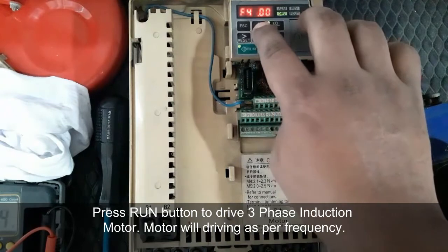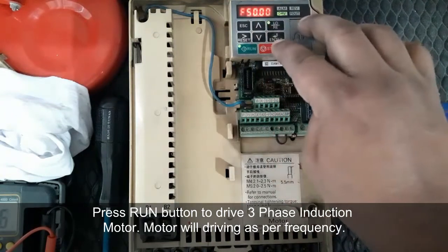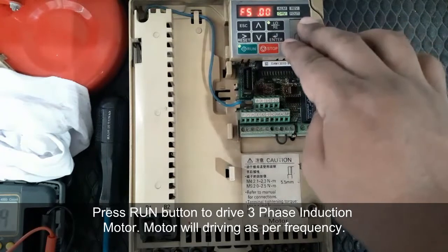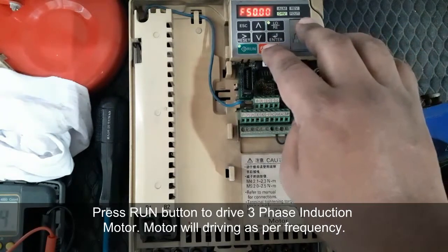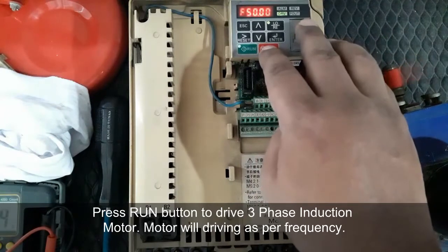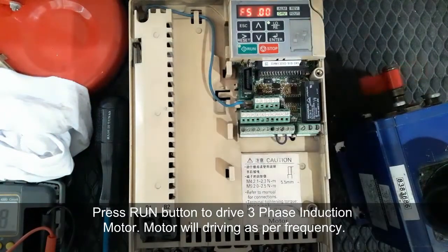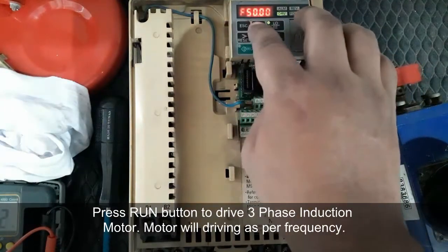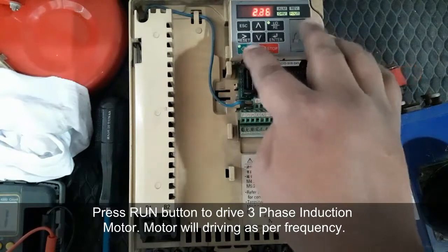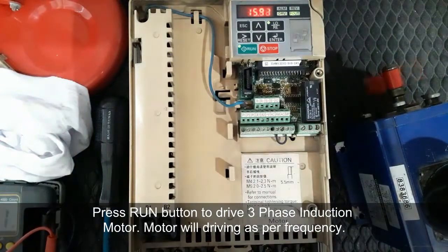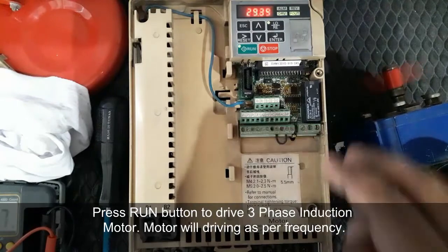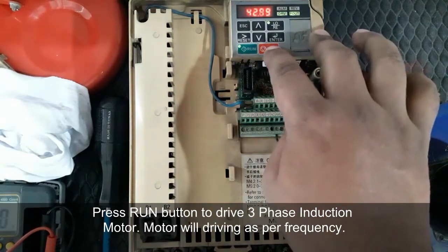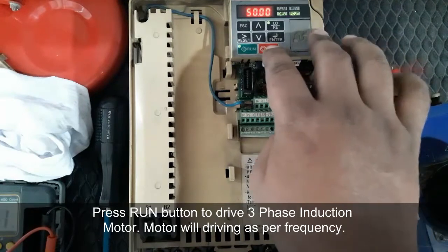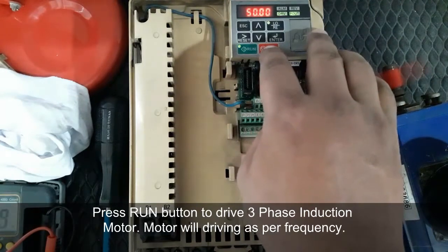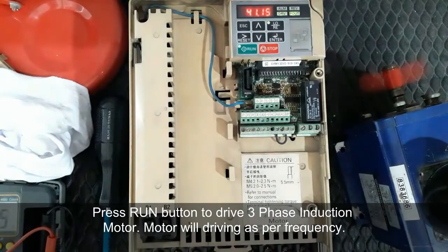Now we want to speed up to 50 Hz. Set 50 Hz and now the motor rotates smoothly at 50 Hz. Look, the speed is 1500 RPM now, and now stop by pressing stop. This is a 3-phase induction motor and it is driven as per the frequency setting. However much we set the frequency, the motor speed will increase or decrease accordingly.